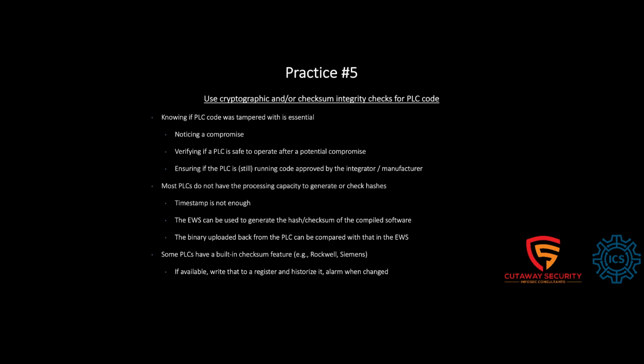Yeah, I think with most PLCs you can have that compiled code binary. I mean, it's available on the engineering workstation, right? And then you can compare that back with what you downloaded or uploaded from the PLC, because even upload and download terminology is different from PLC to PLC. But in my mind, I call anything from the PLC an upload to the engineering workstation. But yeah, with the PLCs that I'm used to working with, you typically get this binary. It's on the engineering workstation as well as you're downloading the same thing to the controller. All right, and that's just a matter of know your tools, right? Right. All right. Thank you. Sorry. Sure.